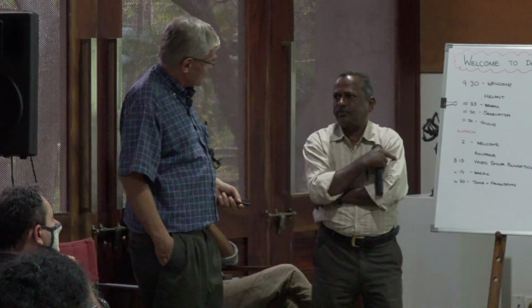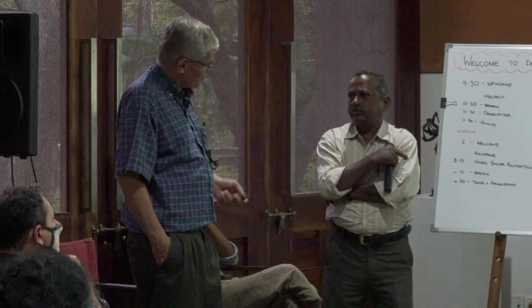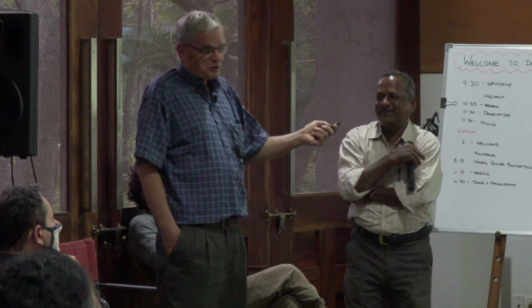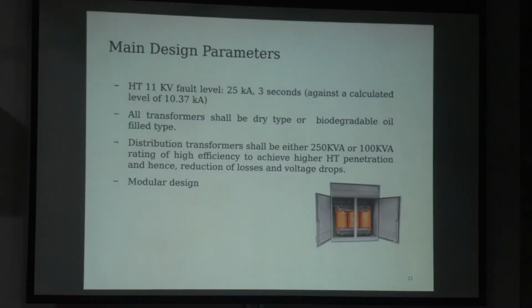Have you installed any transformers beyond 250 kVA? No. Okay, so. No, I just want to check before I commit. So electrical service is not going beyond 250 kVA. So if the load is 500, it will become 2 times 250, 1 here and 1 there. So you bring the high tension closer to the load. And if you do that, you reduce the energy losses tremendously.